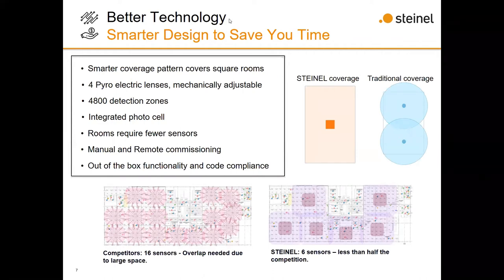No matter how much you tell people not to do that, they wind up in those places, and that can cause issues. Another example was a storage facility where we recommended passive infrared. They ordered dual tech instead, and what they found was all the banging of the garage doors inside the facility caused the ultrasonic sensors to pick up motion and keep the lights on. So all we had to do was go in and turn off the ultrasonic portion. We don't always recommend dual tech. There are places where it's the preferred solution, but there are a lot of places where you can use passive infrared. With our passive infrared being so precise with micromotion, you really don't need dual tech in very many places. Appreciate the question, that's a good one.